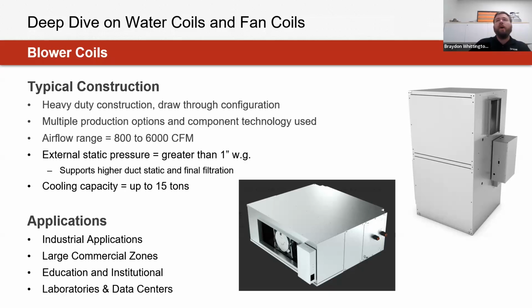But yeah, what you'll notice here as well, a vertical version, but even for this blower coil on screen here too, we're seeing one of these plenum fans installed in them as an option as well. What that's really allowing for us to do, and we learned a little bit earlier, is even more pressure that fan can compensate for. So up to 4 or 5 inches of total static, and higher airflows, which is beneficial for really big systems, or maybe even if any of you do hospital work, where there are requirements for final and pre-filters in systems, or MERV 14 filters for the ASHRAE 170, I want to say, for those spaces. Beneficial for that too, just because now with a bigger or more effective fan, you're able to compensate for these bigger HEPA filters that are being paired with these products there too.